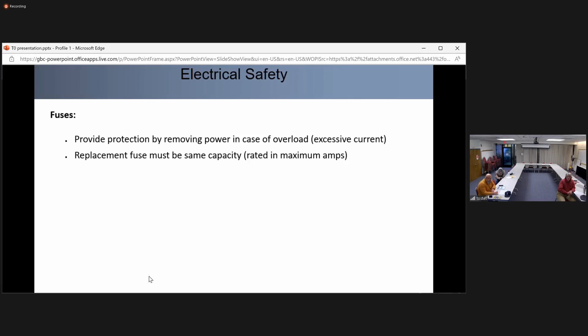When that happens and you go to replace that blown fuse, which has done its job, it sacrificed itself for your safety, you make sure that you replace it with the same capacity fuse. Fuses are rated in the maximum number of amps or amperes that they can conduct before they melt and give up and remove the power from the circuit. So you don't want to replace a 5 amp fuse with a 20 amp fuse, because then the 20 amp fuse would allow more current to flow before failing. And as a result of that, there could be overheating or a fire, because the fuse is oversized and it'll allow too much current to flow in the circuit.